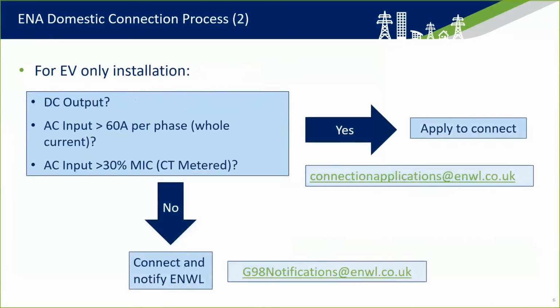For EVs, there are some further specific checks that need to be made. Does it have a DC output, i.e. does it have power electronic equipment? If it's AC output, is it more than 60 amps per phase? For a whole current metered supply, as we'd typically have in a domestic situation, or if it's a CT metered supply, so in a bigger installation, such as a commercial premise, is the AC input more than 30% of the contracted maximum import capacity? So if the answer to any of those is yes, again, it's apply to connect. If it's no to all of them, it's connect and notify. And the email address is given there.